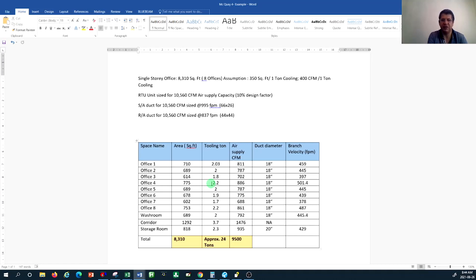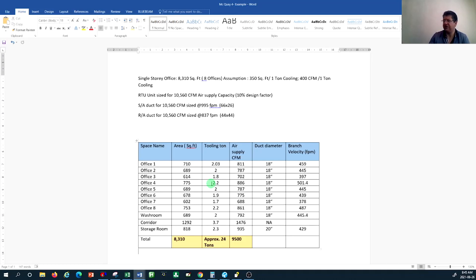For example, if you are in a smaller space like a classroom where the noise level is very important, you might want to watch the velocity in the duct work with that specific size. Even if you're sizing your duct work based on 0.1 inch water column per 100 feet of length for equal friction, the velocity might still be a lot higher — so you want to consider all of these factors.